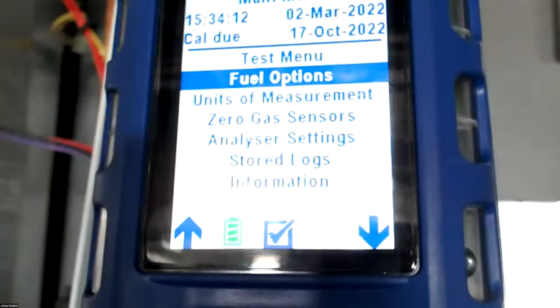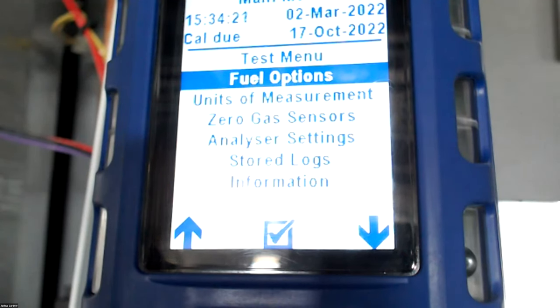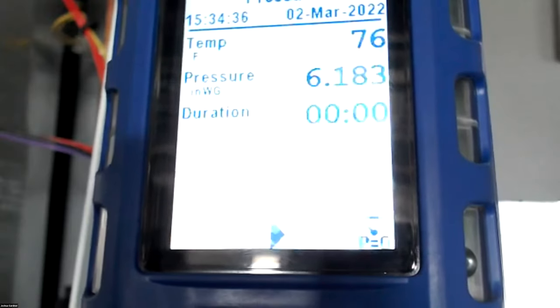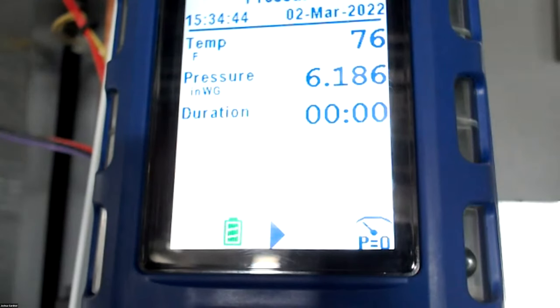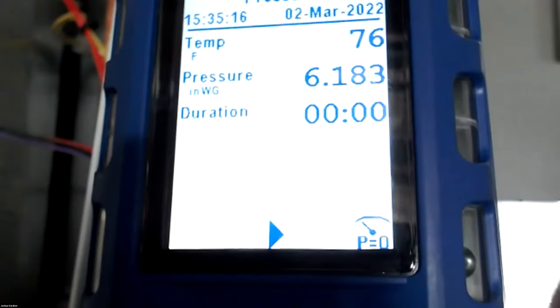So let me grab. We're on natural gas here. For natural gas, we're looking for 5 to 13 inches water column on our gas pressure. And I'm at 6.1. Propane, you're going to be looking at 8 to 13 inches. And all this info is 100% in our manual, so if you don't remember, it's okay. But those are the pressures that we need, and we don't want to drop more than 1 inch. So that's one thing we need to watch out for when we get in high fire, that we're not dropping 1 inch from static to high fire. And we'll just escape out of here.